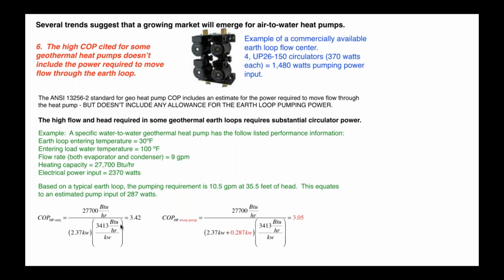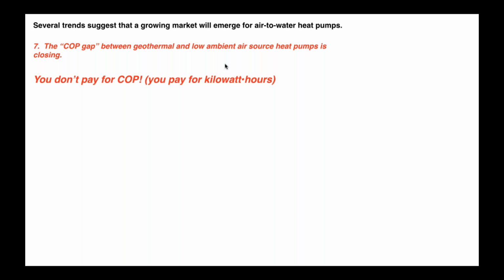It takes that COP from perhaps a published value for the heat pump only, 3.4, down to about almost 3.0. So as we throw more and more pumping power at a geothermal earth loop, we're actually taking away from the true system COP. All right. And again, if you're doing geo, it's not my purpose to just shoot a bunch of holes in the geo market by any means. But realistically and from an engineering standpoint, you should be including the cost to operate the earth loop circulator as well as the heat pump itself, because that is what your customer is going to pay for. And by the way, you don't pay for COP.